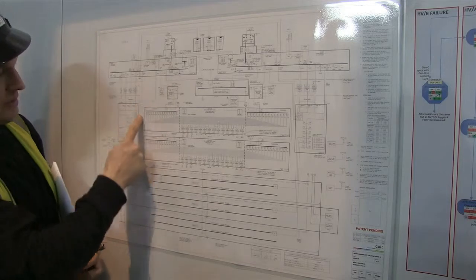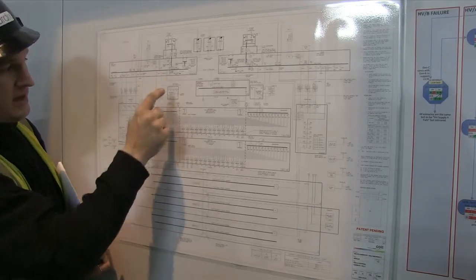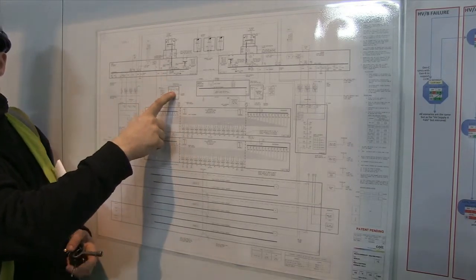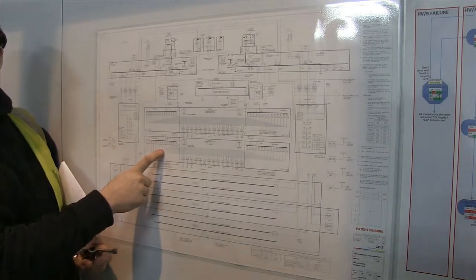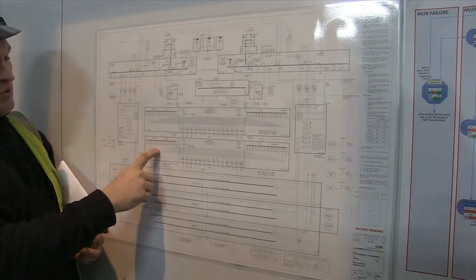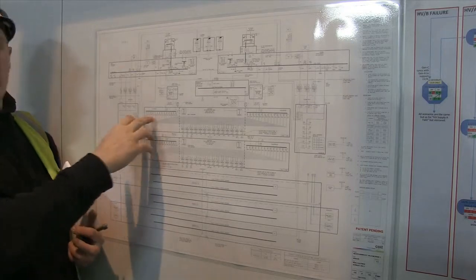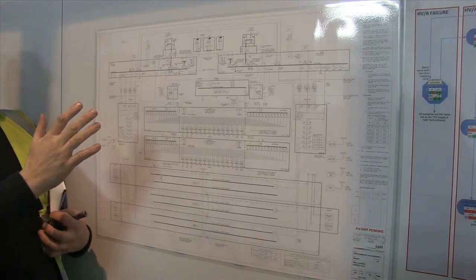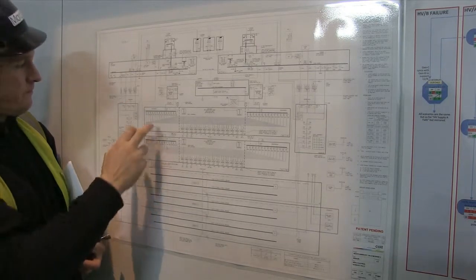So the difference between that panel there and that panel there is that's mechanically fed by the UPSs and that panel isn't. So if you get a mains failure, that will go over to its alternative supply. That one won't, in reality, won't really see the loss of supply unless you killed the UPS.